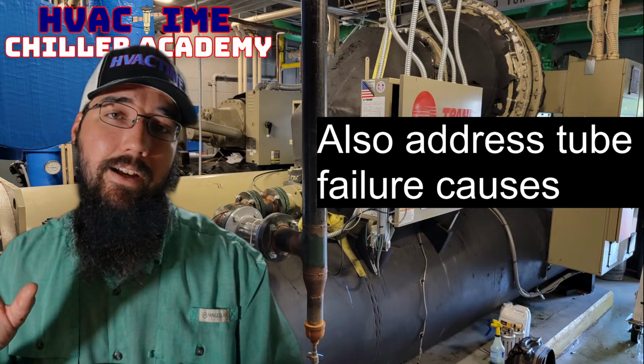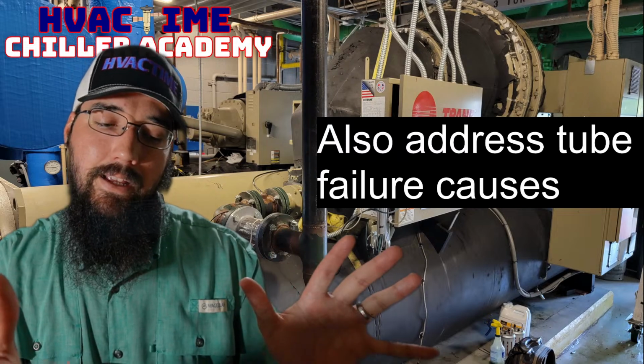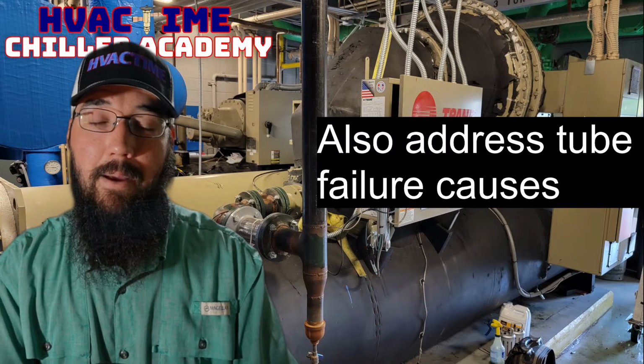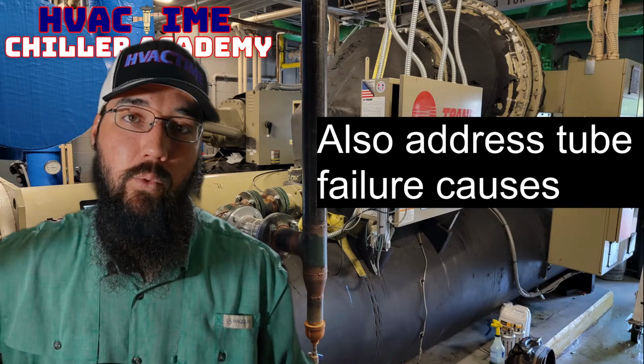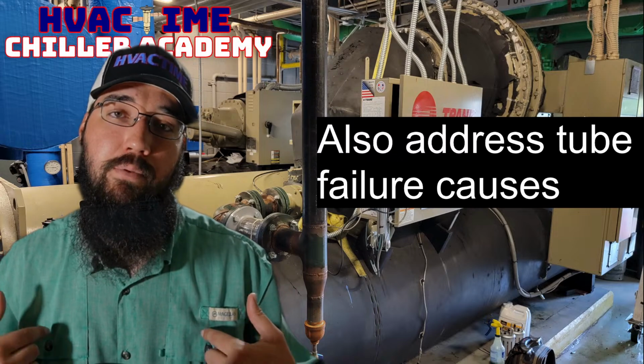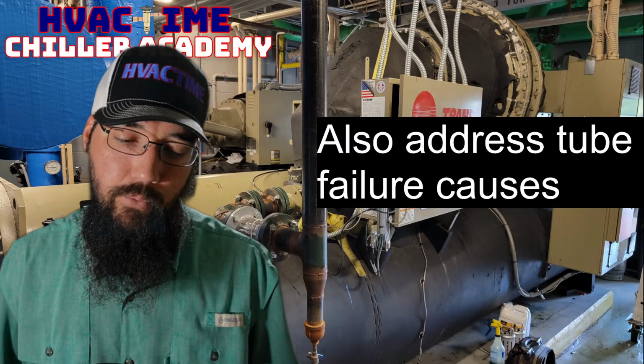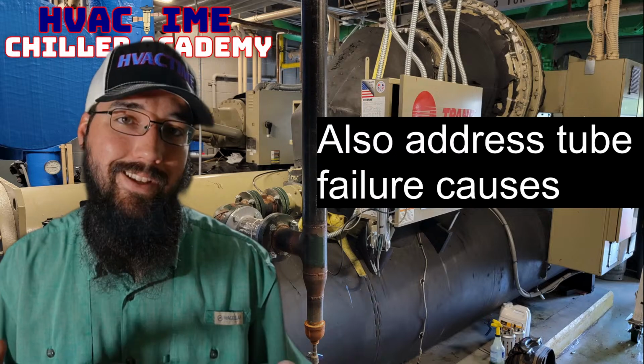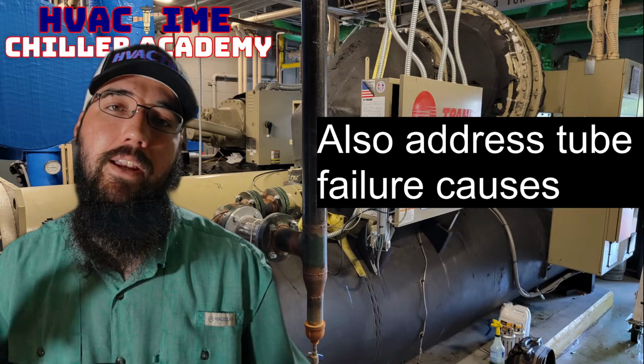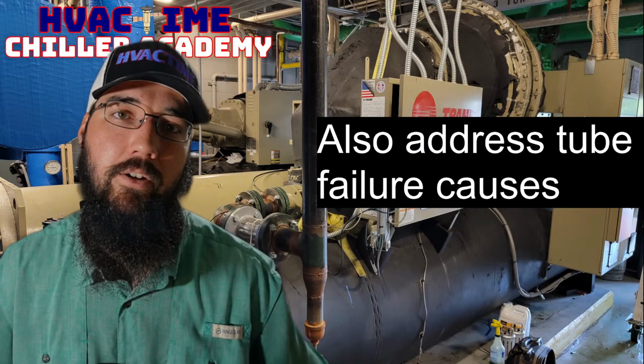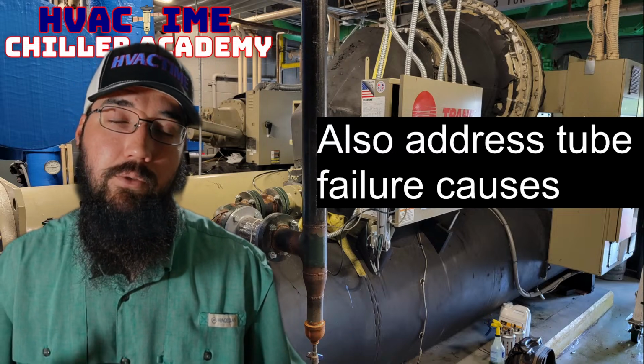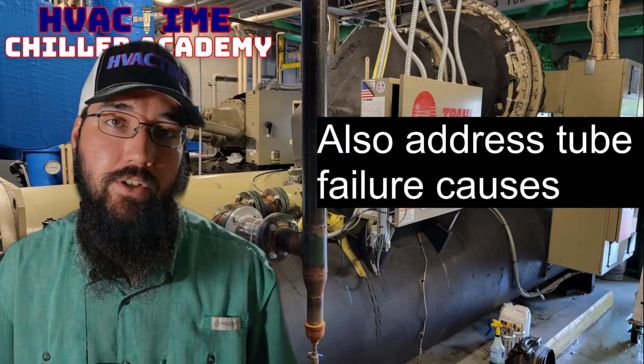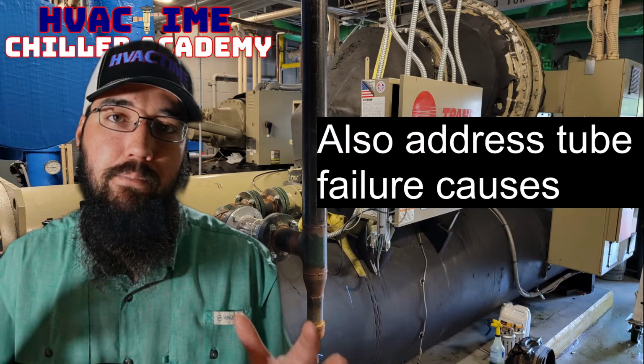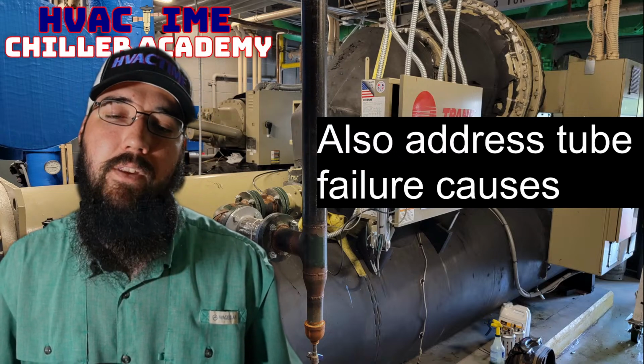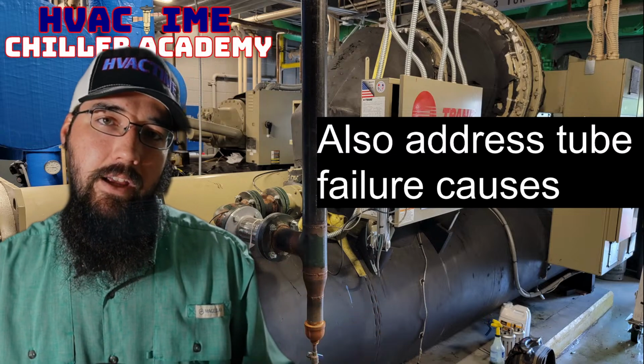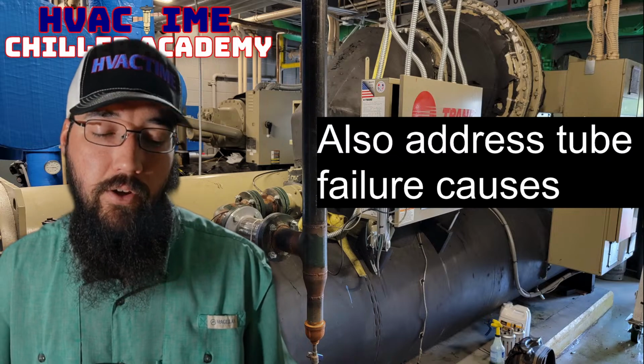Frylock knows about this one. There's a property that we've worked at where some of the pump strainers had collapsed and disintegrated into a bunch of different pieces and made their way through the piping network. Most of the time, our pumps are going to be pushing directly into our chiller. So in this case, those little fragments got into the condenser specifically, and they were big enough and sharp enough that as they went through the condenser, they just started punching holes on their way through. Technically it was two different chillers, but it led to having to plug a bunch of those tubes until we had exceeded the amount we could plug and still have any reasonable amount of function, in addition to just trying to stop the leaks in general. So having debris that is able to puncture a tube is another way to have a tube failure.